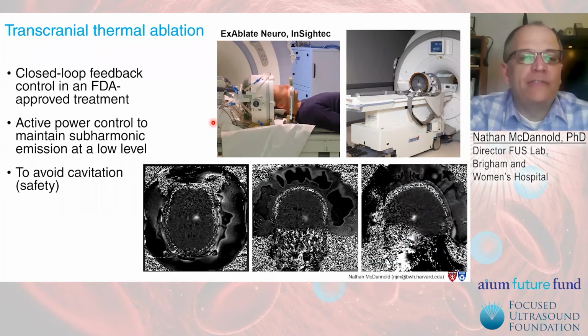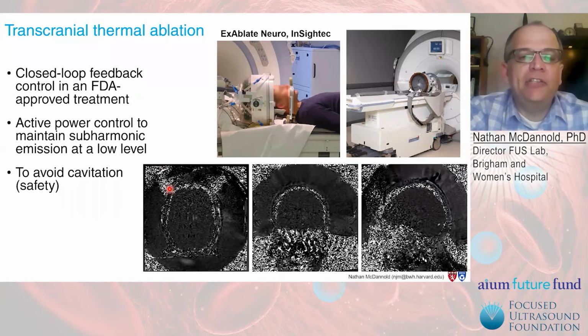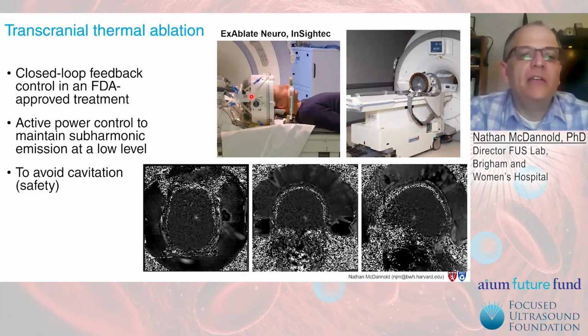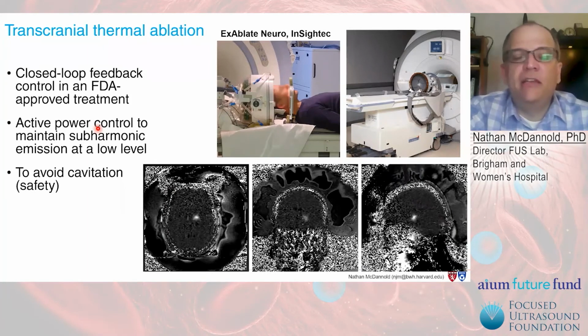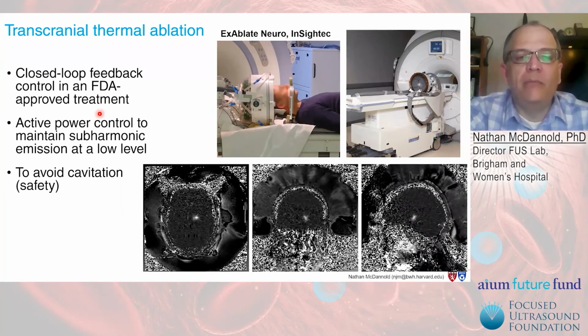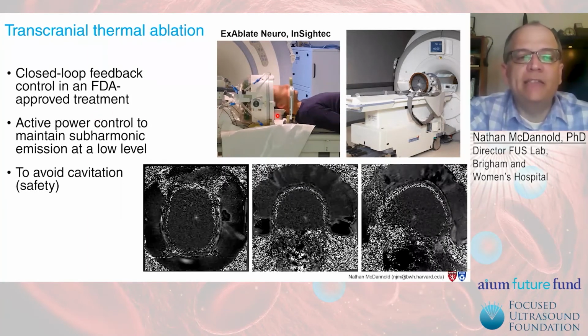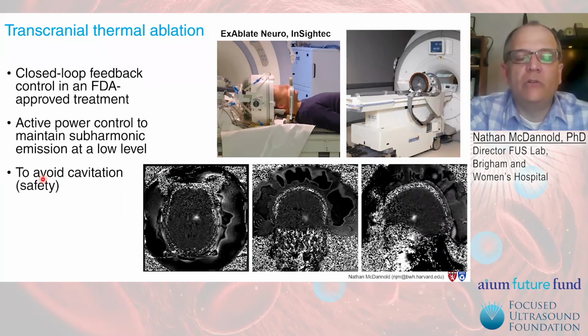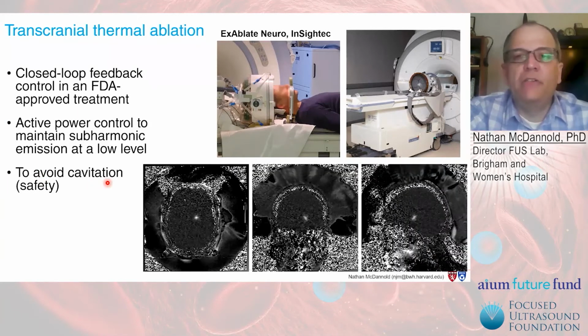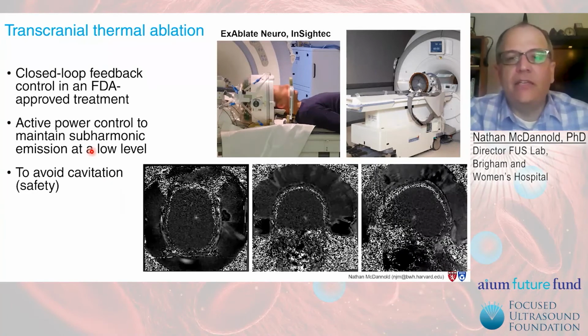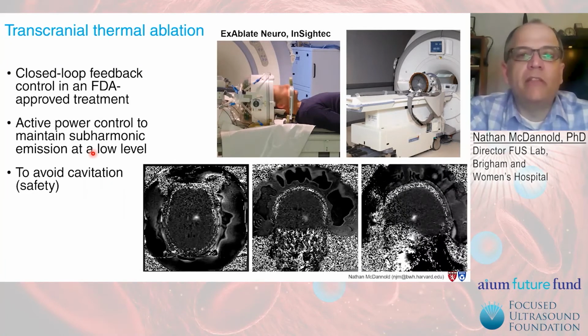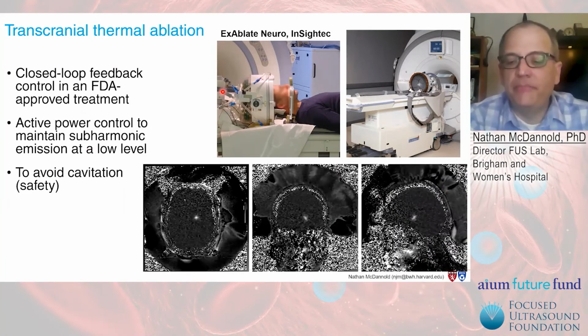And this is for safety. So during each sonication, the detectors built into the helmet monitor for subharmonic emission. And if it's detected, it will automatically lower the power in real time to maintain a safe level. And the goal here is to avoid cavitation for safety. If you have inertial cavitation, there's a risk of hemorrhage, and they don't want this in this thermal ablation treatment.